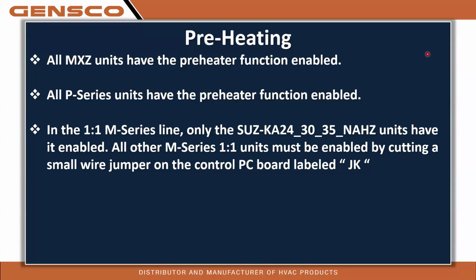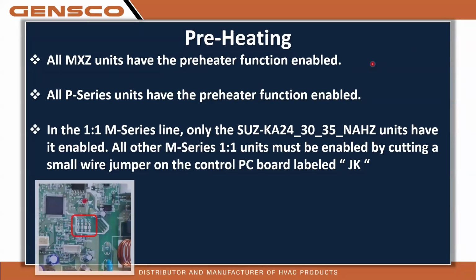Now, all MXZ units have the preheat function enabled, and all P series have the preheat function enabled. The ones you have to worry about are the M series one-to-one systems. In that line, only the SUZ-KA24, 30 and 35 hyperheat units have it enabled, because those units are actually P series hyperheat units. The other M series one-to-one units, this function must be enabled by cutting a small wire jumper on the control PC board, which is labeled JK.